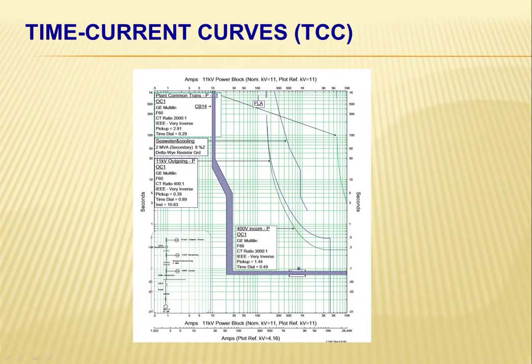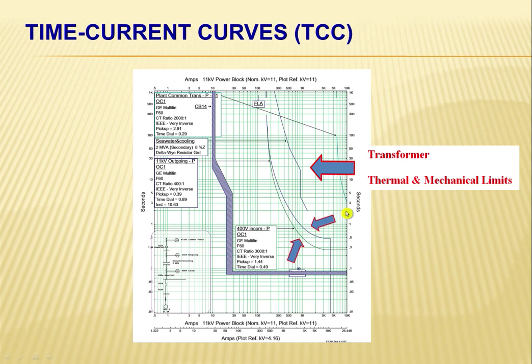This is our time current curves. This is the curve for our subject relay. This is also the relay for the secondary, and this is the relay for the primary side of the transformer. And we have here the transformer thermal and mechanical damage curve. By looking at these curves, we could conclude that our transformer is being protected by both primary and secondary protection relays.